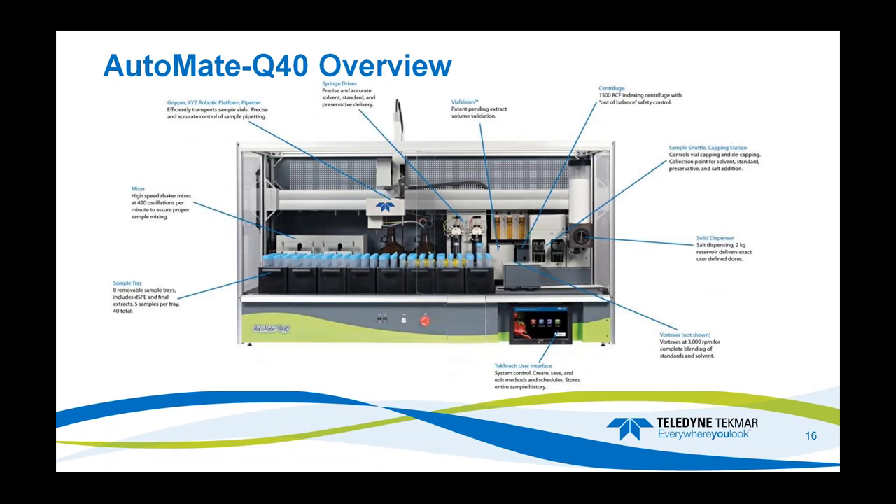Here is an overview of the unit itself. There are eight trays that hold five samples apiece, giving you 40 samples. In the back left-hand corner is the shaker. The pumps and syringe drives deliver a precise and accurate amount of solvent or standard to the sample. The centrifuge meets all European and AOAC method requirements. The sample shuttle and capping station is where the vials are capped, decapped, and solvent is added to the sample. The solid dispenser adds the extraction salts. There is also a vortexer and a touch screen interface to run samples and make schedules and methods.